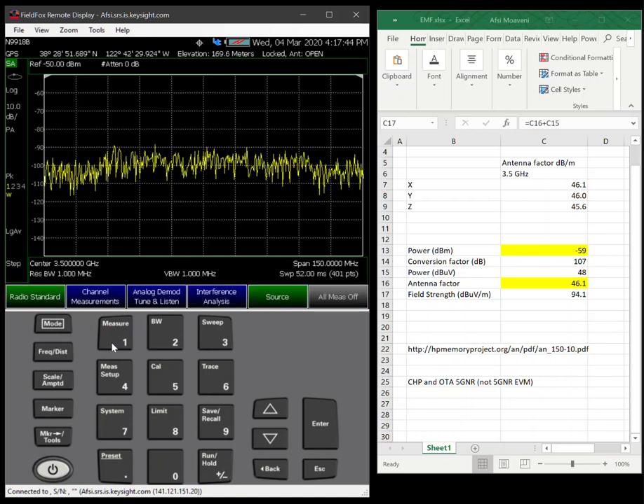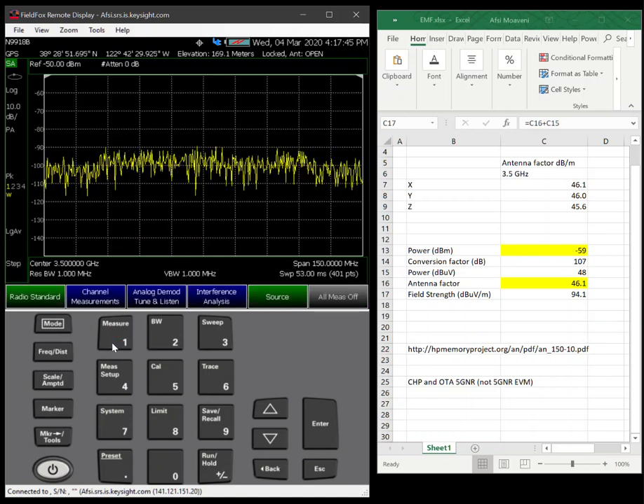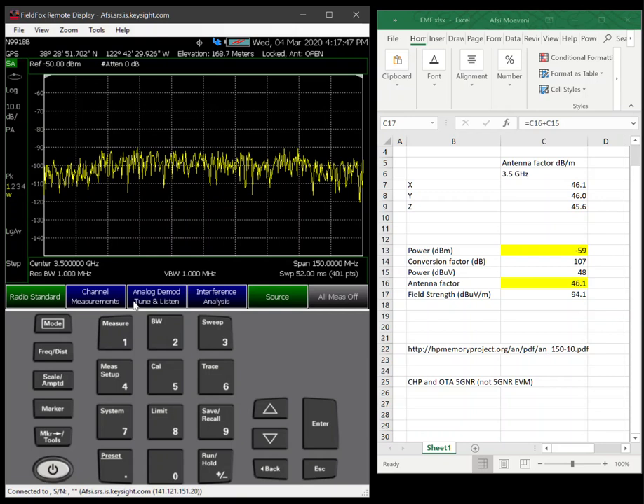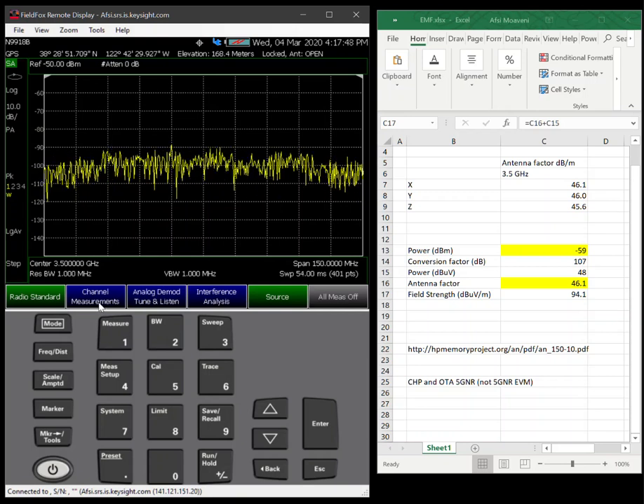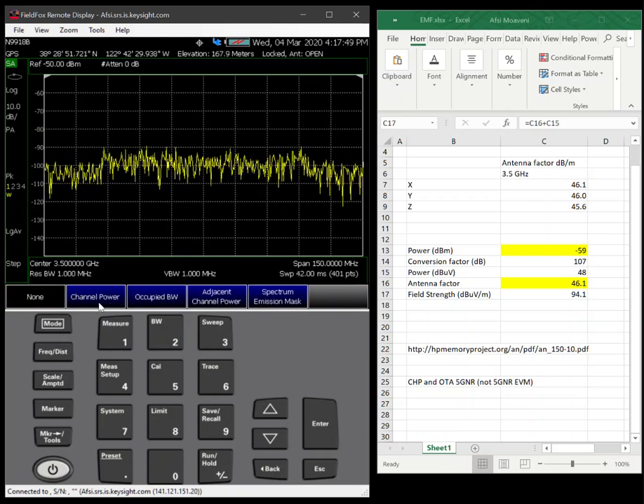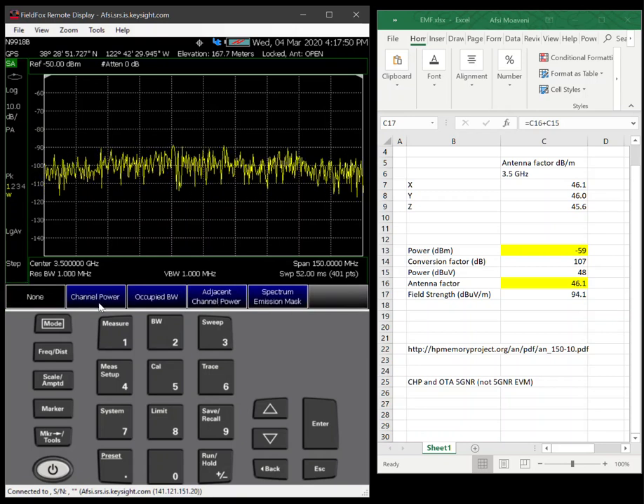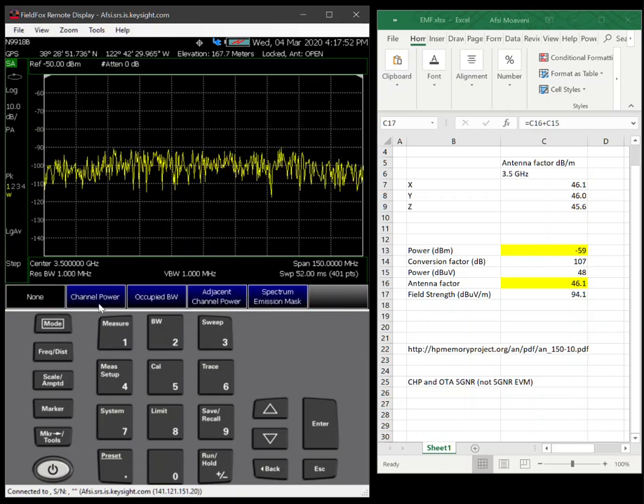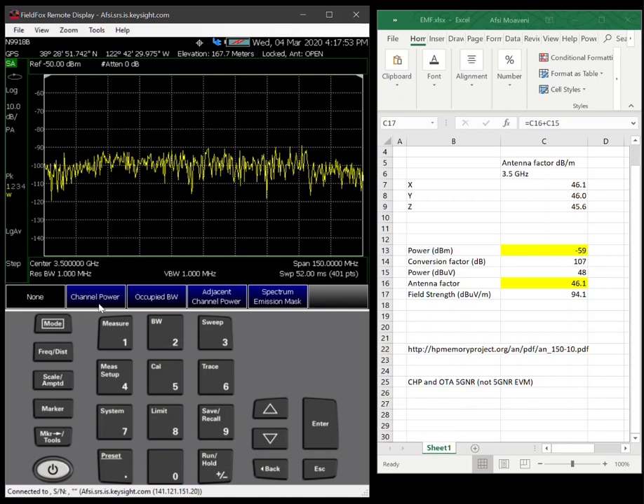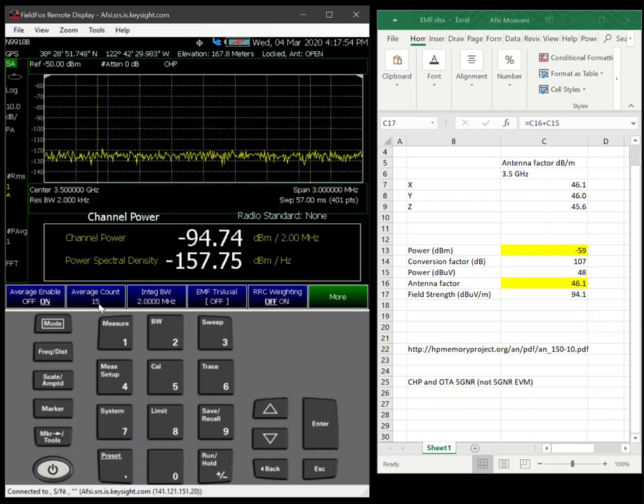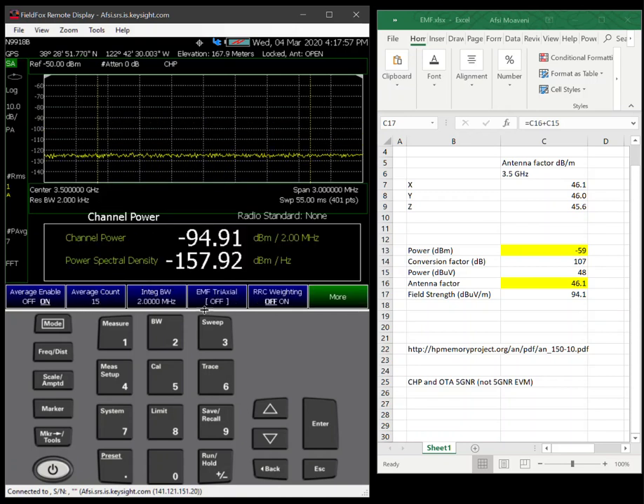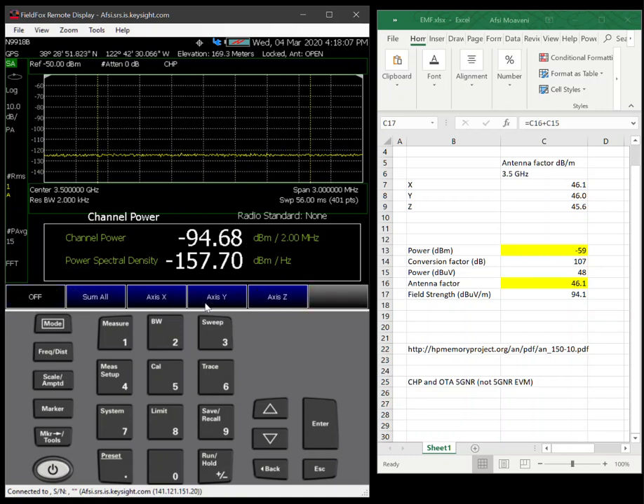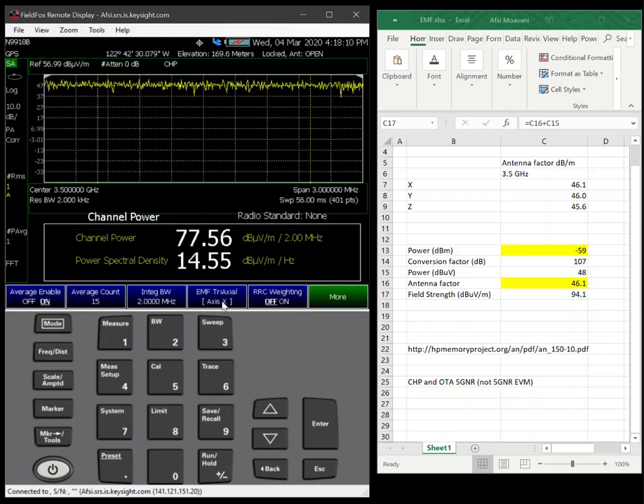Now we come in here, and the place where you can control the antenna is Channel Measurements. Under Channel Measurements, Channel Power is the only place in SA mode where you can measure the integrated power of all three elements. When you go into Channel Power, the soft key shows up called EMF Triaxial. This is the soft key you get with option 358 and with the antenna. You can look at the power in each axis or generally you would say the power in all of it.